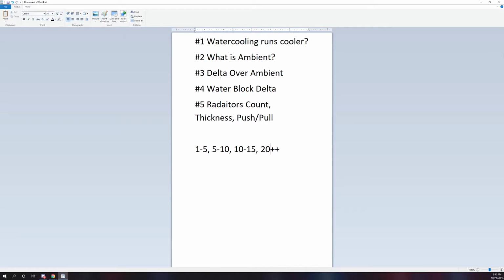This is what they mean by delta over ambient: the difference between the temperature of your water and the ambient temperature, right? So just now, I know it's 30 degrees in here. My delta is 2 degrees. 1 to 5 is ideal, okay? 5 to 10 is good. 10 to 15 needs improvement. 20 is you have a problem, okay?